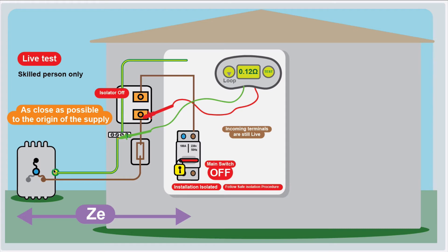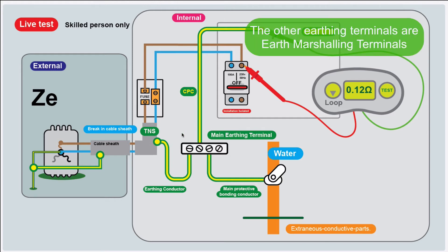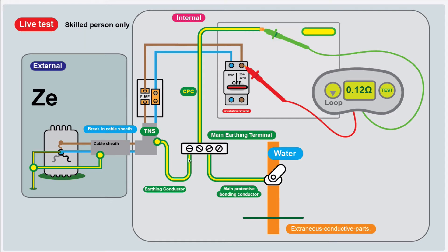We also want to check the earthing conductor because there might be other connections off the main earthing terminal. If there are other connections coming off it, you could be getting parallel paths. If we have an isolator or switch fuse before our consumer unit or distribution board, we take our ZE reading from there. Now let's look at the main earthing terminal. We're going to test between line and earth at the consumer unit — there's no switch fuse beforehand, just a service cutout, so I'm okay to test from here.